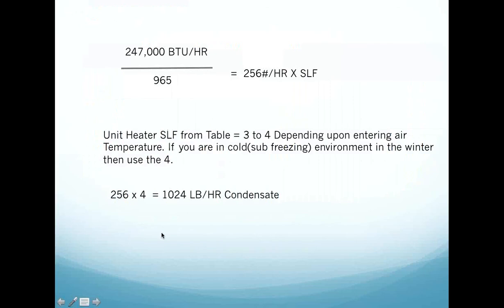So the simple math becomes this: 247,000 BTUs per hour divided by the 965, which is nothing more than the latent heat of the steam at the steam pressure we provide the heater, is 256 pounds per hour. And then I want you to put a safety load factor on that number. The safety load factor is 3 to 4. And if you live in my area, in the northern part of the United States, in upper Washington State, we can see sub-freezing conditions. So I'm going to use a safety load factor of 4.